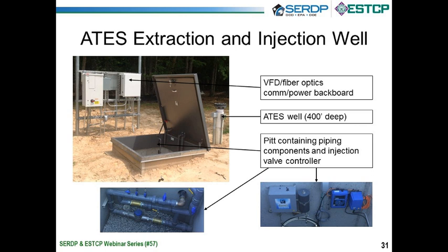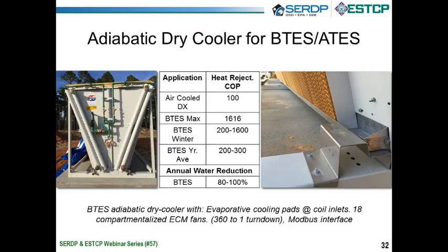There are a lot of ways to do these systems wrong, but if you understand the hydrogeology and the water chemistry, they can be trouble-free. Some of these systems in the Netherlands have run 30 years without ever having to backflush the wells. Certainly we did a lot of work to make sure we're not moving sand in and out and that we're not doing anything to the geochemistry of the water, so that it's happy. We pull it out of there the way it came, we change it a few degrees, we put it back, and we live happily ever after.